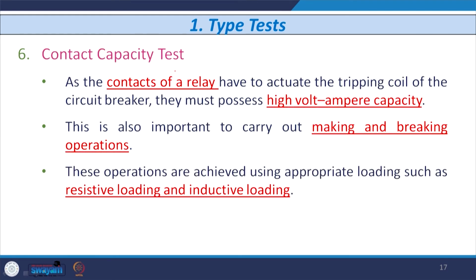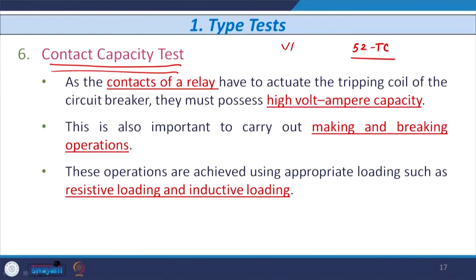The next test is known as the contact capacity test. We know that the contacts of the relay have to actuate the tripping circuit or tripping coil of the circuit breaker. As I told you, it is 52 TC, the trip coil of the circuit breaker, where 52 is the number given to the circuit breaker. So, the contacts of the relay have to actuate the trip coil of the circuit breaker, and they must possess high volt-ampere capacity. The VA capacity of the relay contact needs to be defined by each and every manufacturer.